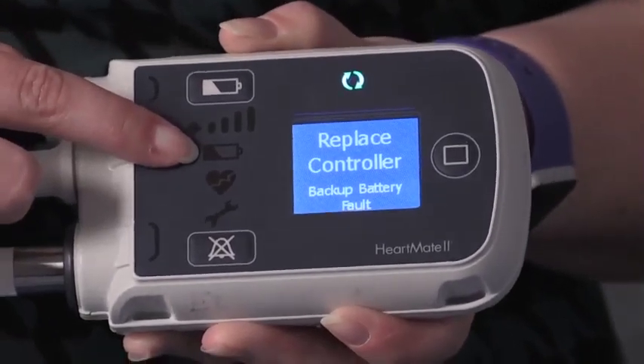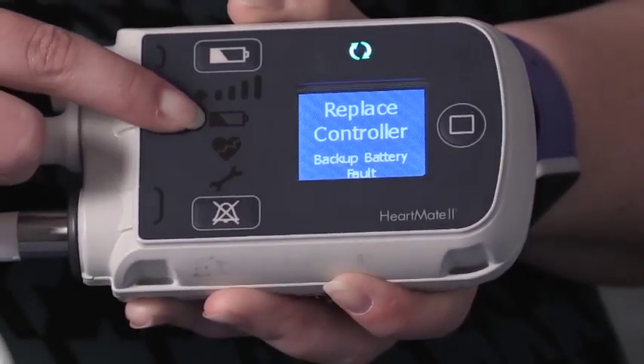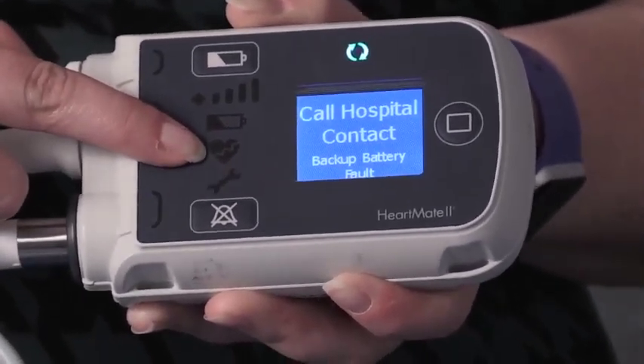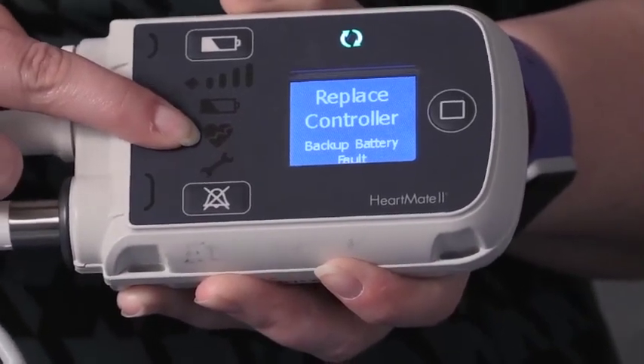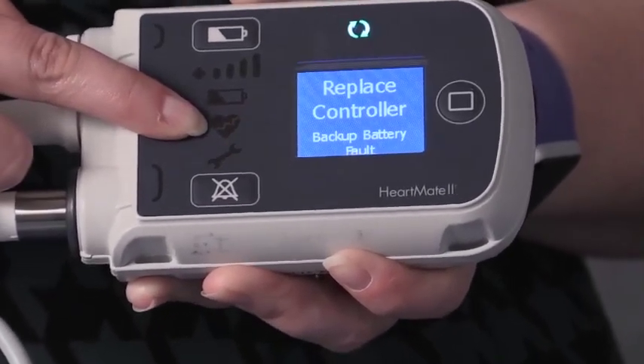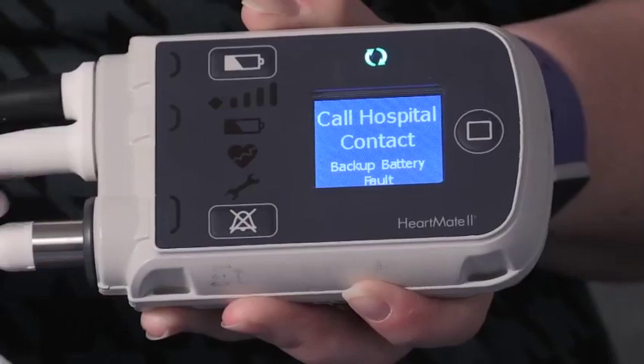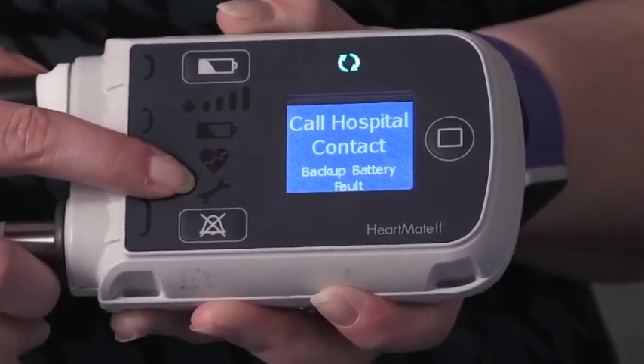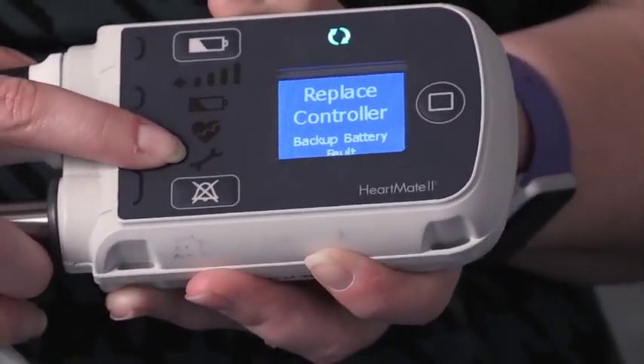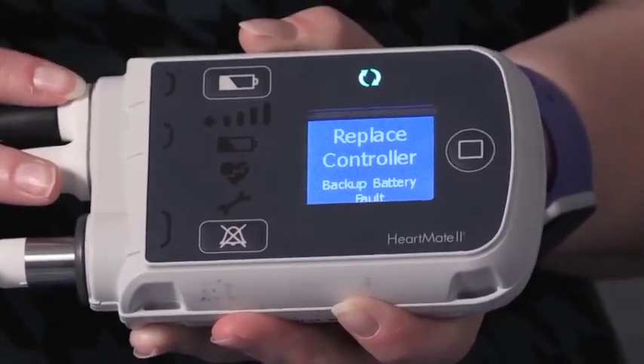And the red battery comes on when you have 5 minutes left. Our broken red heart here goes off when there is something wrong with the pump itself. Typically that's a low flow alarm. As you can see on this controller, our yellow wrench is alarming. And what that means is that there's a computer glitch with the controller itself.